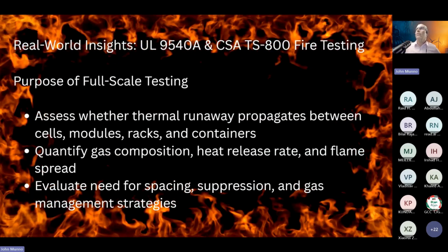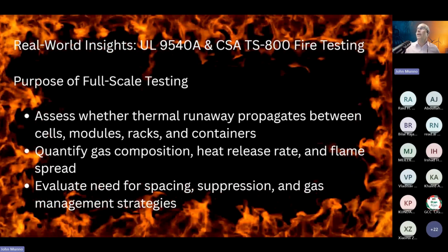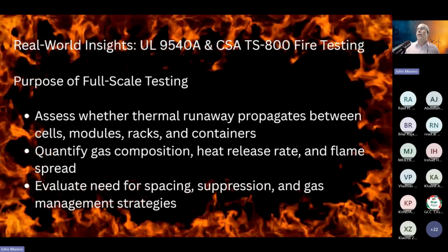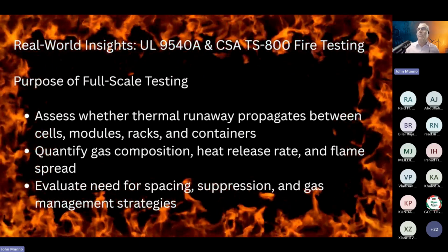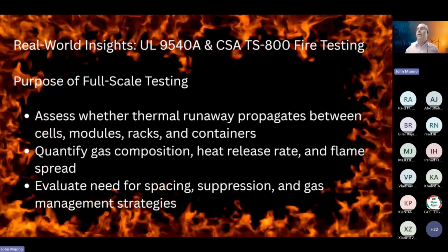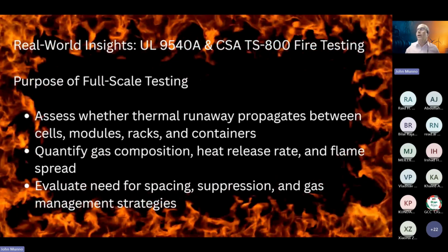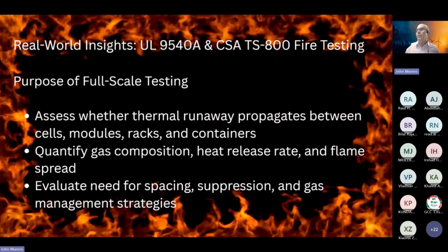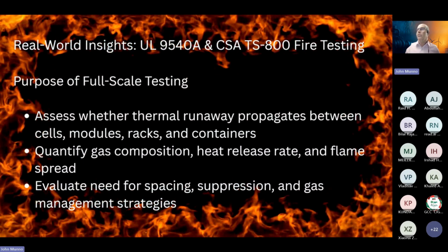So what is 9540A and CSA TS-800 fire testing? Well, it's full-scale testing, and it's there to determine whether thermal runaway propagates between cells, modules, racks, and containers. And it's there to quantify the gas composition, the heat release rate, and the flame spread. And believe it or not, there's not a pass-fail criteria. What it does is it just documents what happens when a cell is put into thermal runaway. Does it propagate to the next cell? Will it propagate through a module to adjacent modules? Will it propagate across racks or beyond containers? So it's there to just give us information. 9540A is not a pass-fail test.